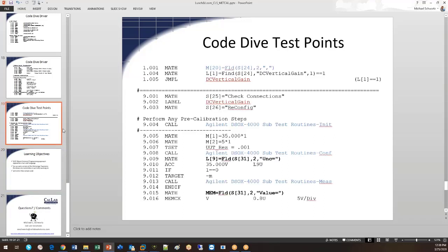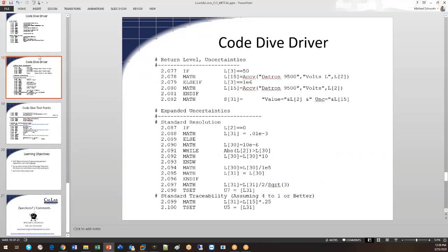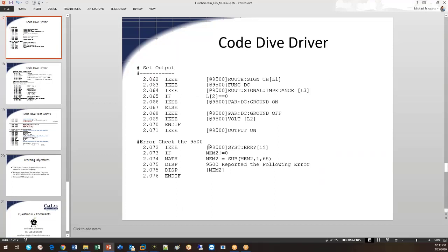Yeah, so we add it in as an alias, but we're handling the flexibility with the drivers. So when you look at our aliases in here, we're going to use at 9500 as our alias. So you can use any aliases that you want inside of that driver. And then the newer versions of MetCal will let you have multiple aliases. But the problem with making it a DC voltage source is then you can only have one DC voltage source.